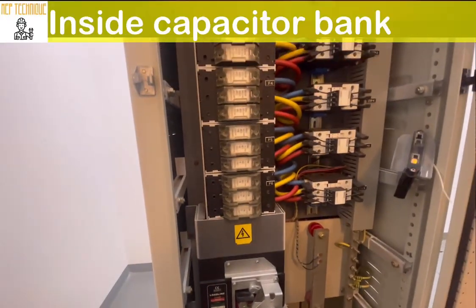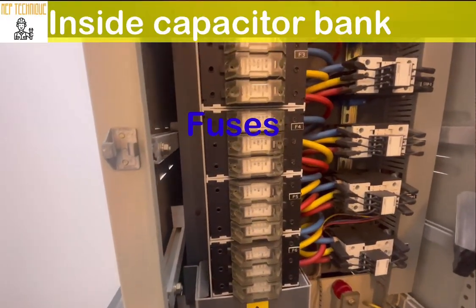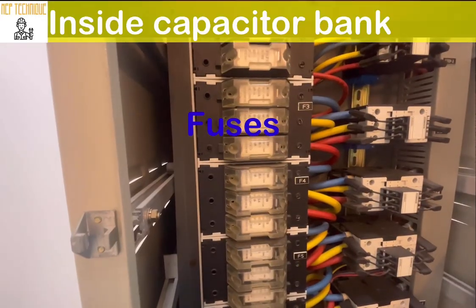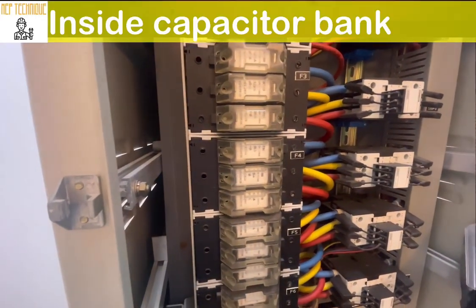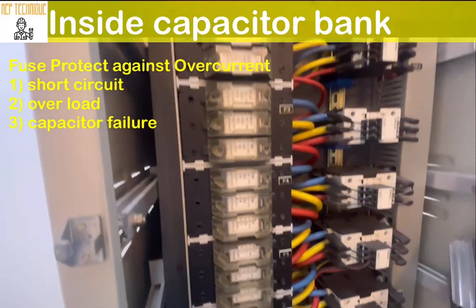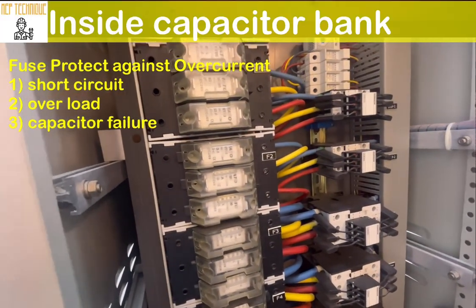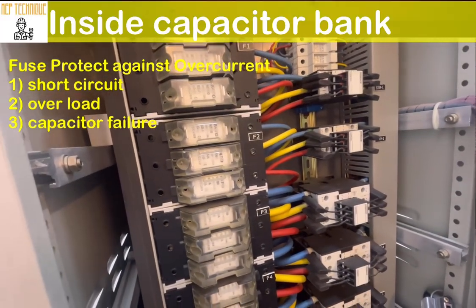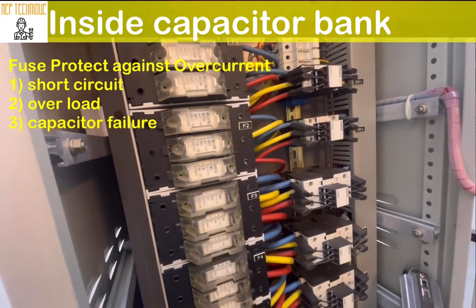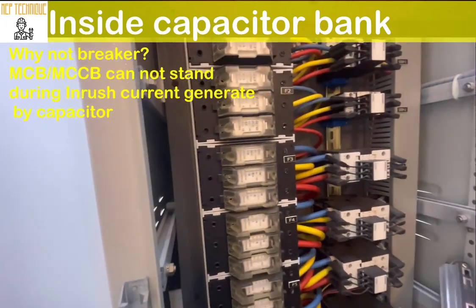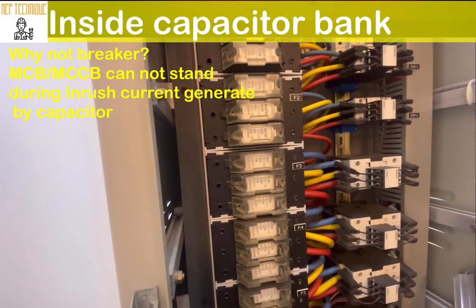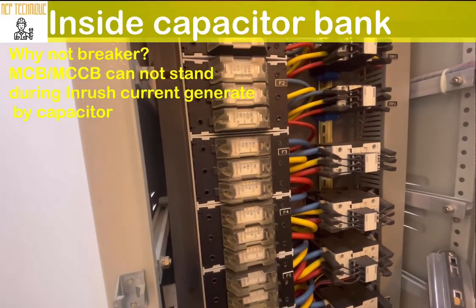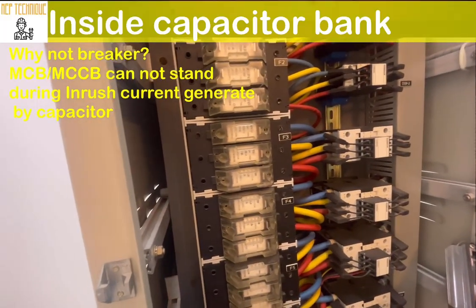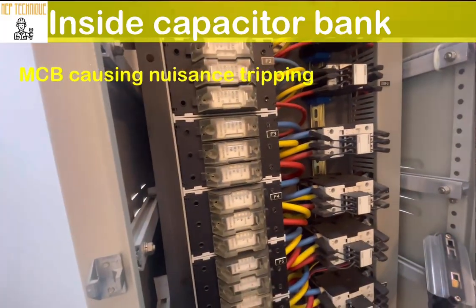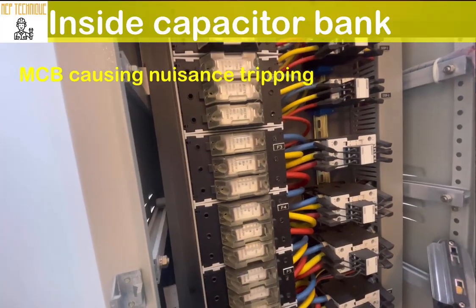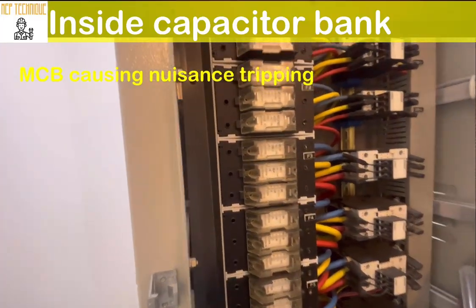After the isolator, it is connected by the bus bar with a fuse, where there is a fuse inside the capacitor bank, because it is protecting against faults, disconnecting when overcurrent flows into the circuit during a short circuit or any overload or capacitor failures. The question is why we cannot use MCB or MCCB instead of a fuse. Because the MCB cannot handle the inrush current generated by the capacitor, and the MCB causes nuisance tripping. That's why we use a fuse.